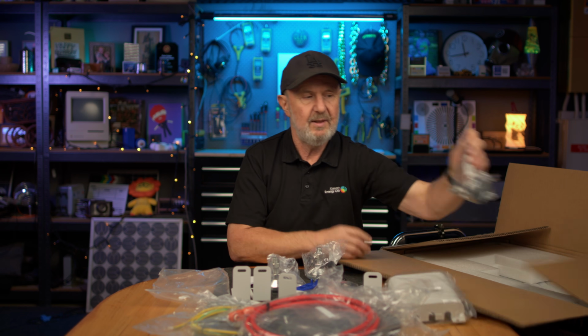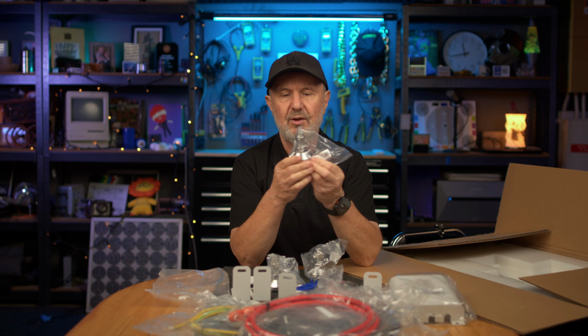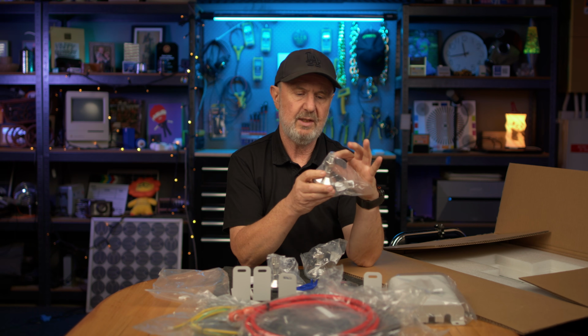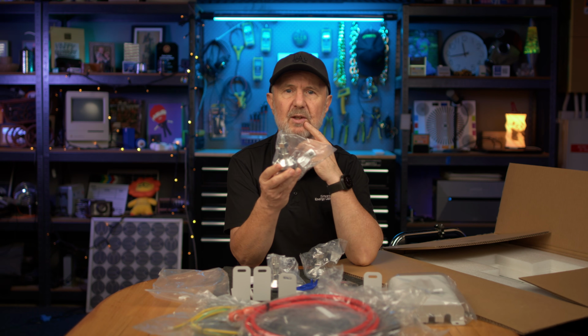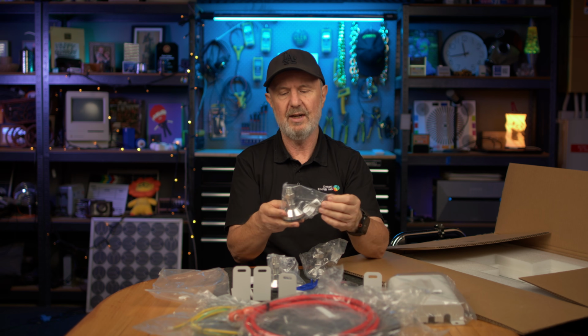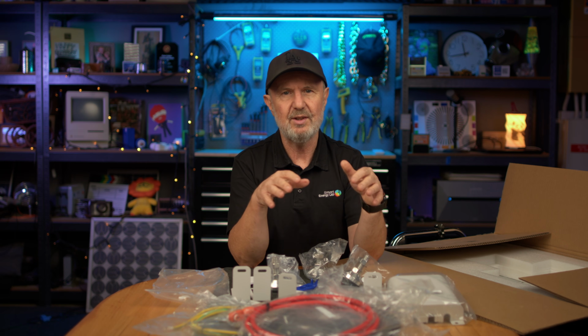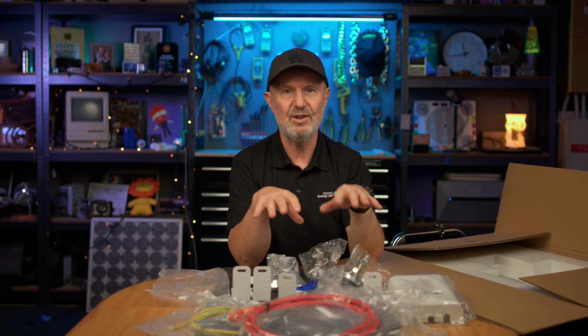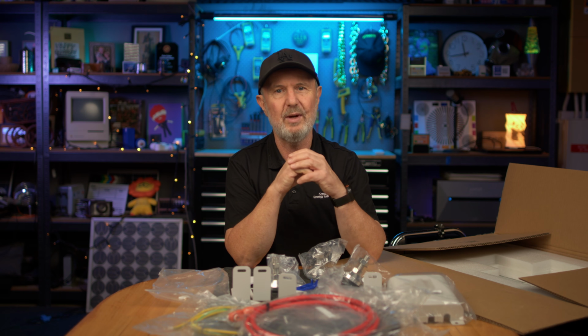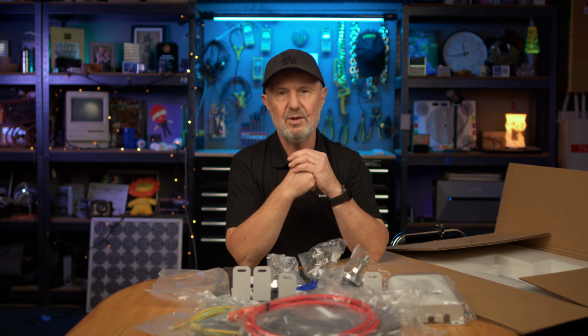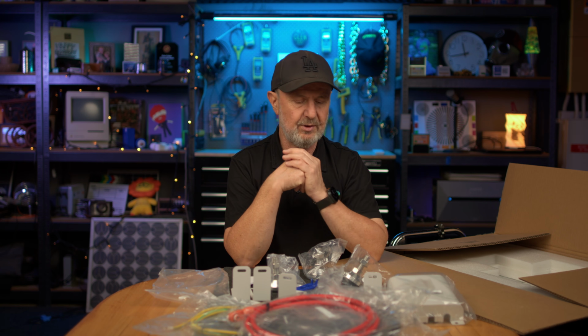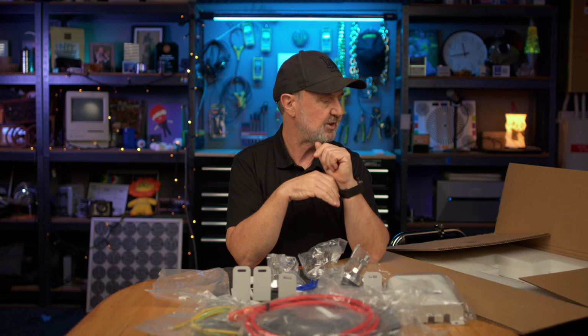These are adjustable for height, so you've got something like 20 to 25 mils of adjustment on these feet to suit uneven ground. But you should still ensure that the ground underneath is secure, it's not just a bit of dirt that's going to get wet and subside. So make sure you've got a stable platform to put the battery system on, particularly if it's going outside.